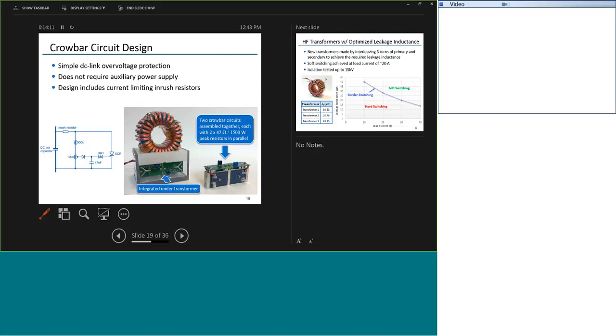The crowbar circuit measures the DC link capacitor using this voltage divider shown here that then triggers the SCR device when the DC link capacitor voltage is too high. The inrush resistor limits the inrush current, and our protection scheme triggers within milliseconds or below after the inrush current is detected. So the inrush resistors are shown here. They're sized to sustain the inrush current for a short period of time to minimize the system size.